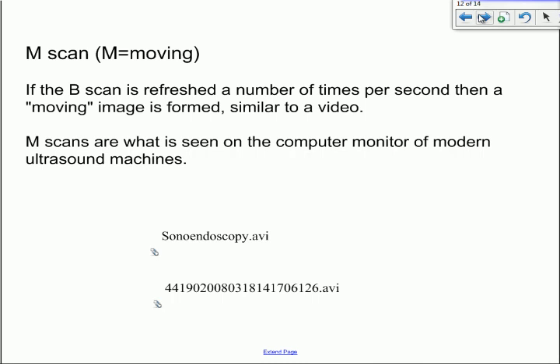And then there's an M scan, where M stands for moving. So, effectively, what we do is we take a B scan every tenth of a second or whatever, and we refresh it like a TV picture, which effectively gives us a moving image, just like a film. So many A scans making up a B scan, and a few B scans a second making up what we call an M scan.